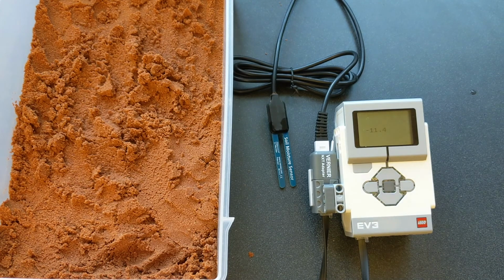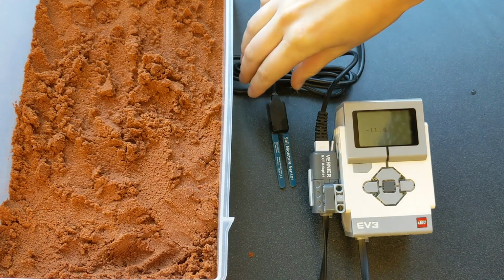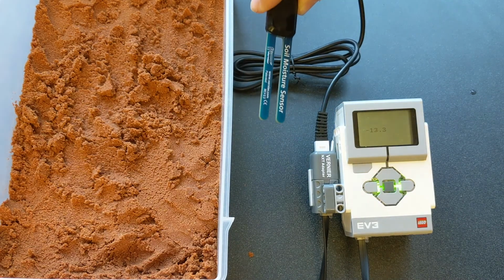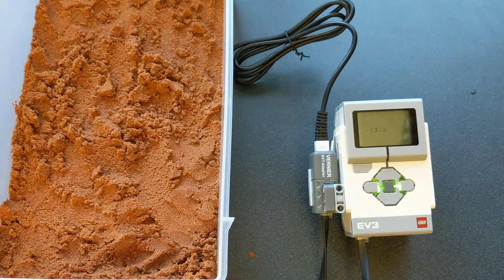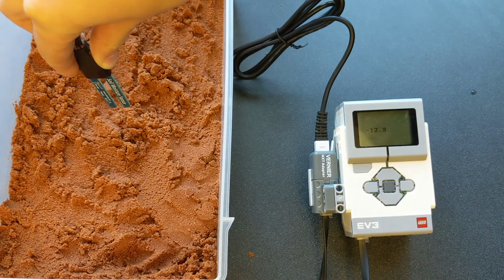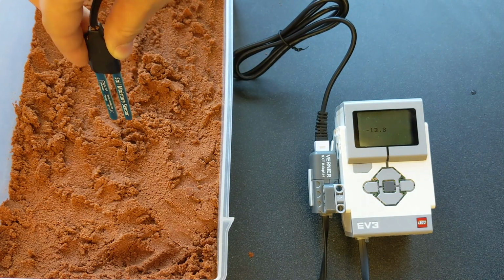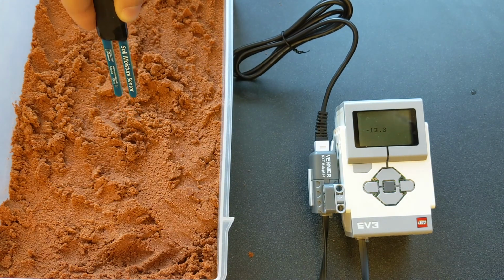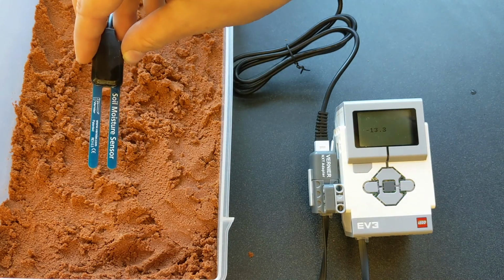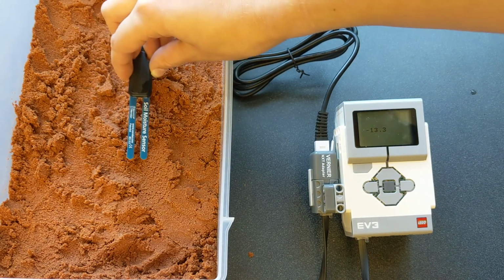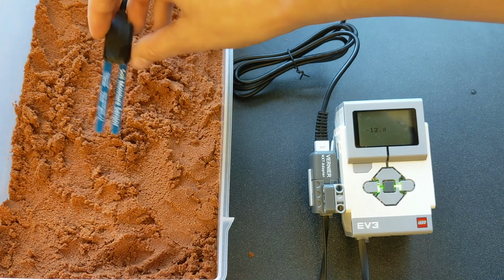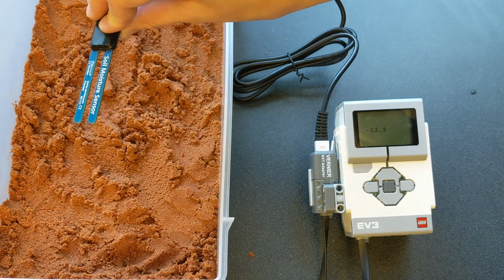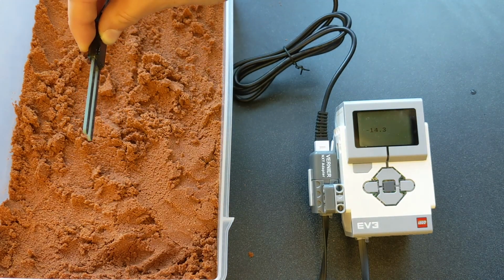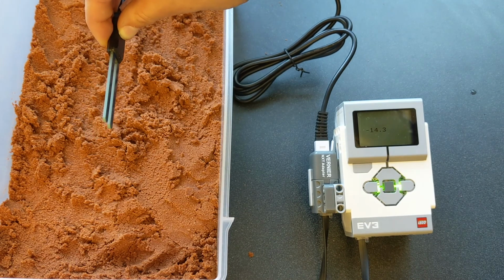Here we have some lovely red sand, and we want to know how much water is in it. So we'll use our moisture sensing probe. We're not going to stick it straight down because moisture can vary by depth, and we'll get a different reading at each end, and that won't be an accurate reading. We're also not going to stick it in flat because water might settle on the flat parts and interfere with our reading. So instead, what we're going to do is stick it in like this, kind of like a knife.